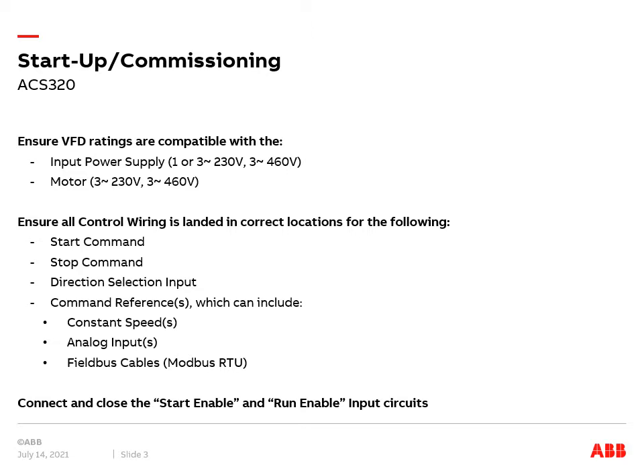Ensure any start enable or run enable safety interlocks are jumpered out in the control wiring. This is achieved by wiring either plus 24 volts DC or 0 volts DC to their respective digital inputs for either PNP or NPN wiring configurations.